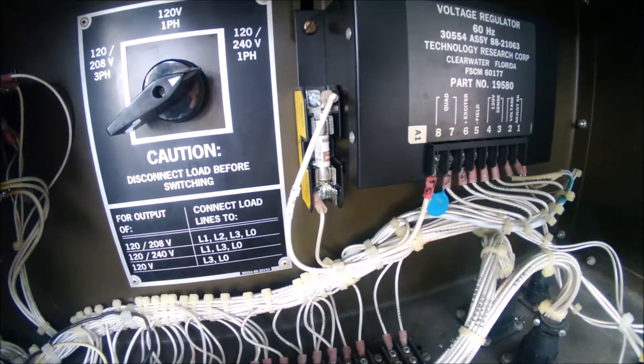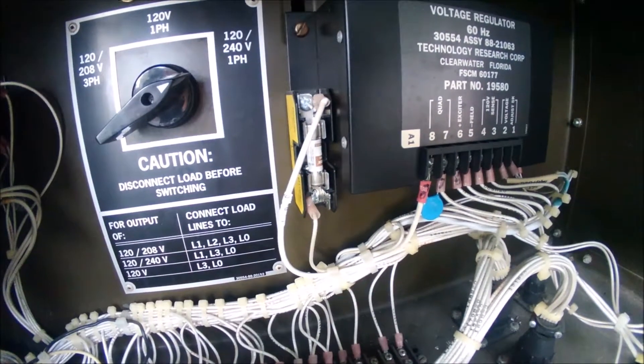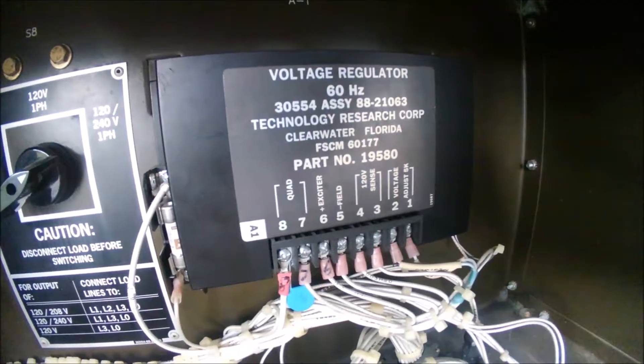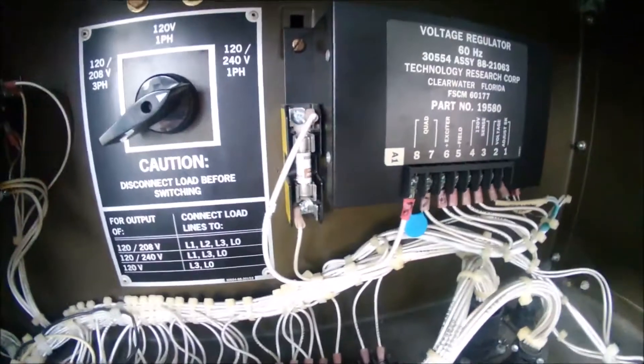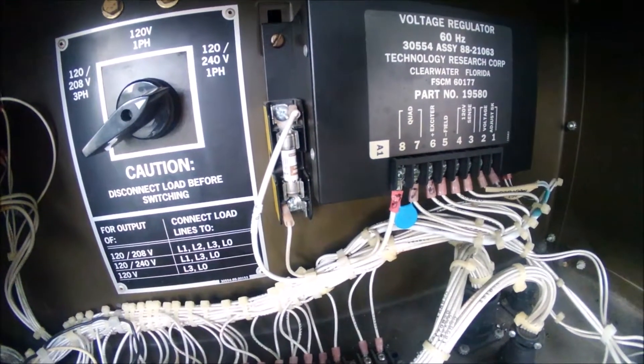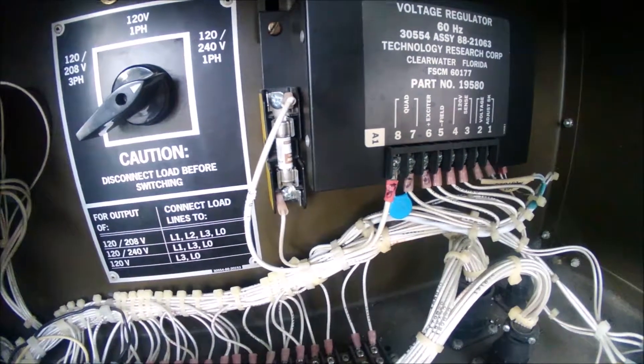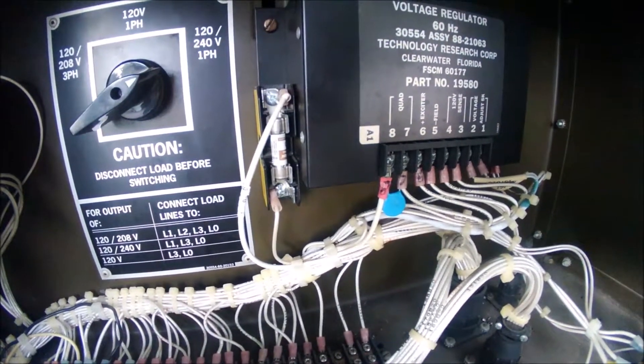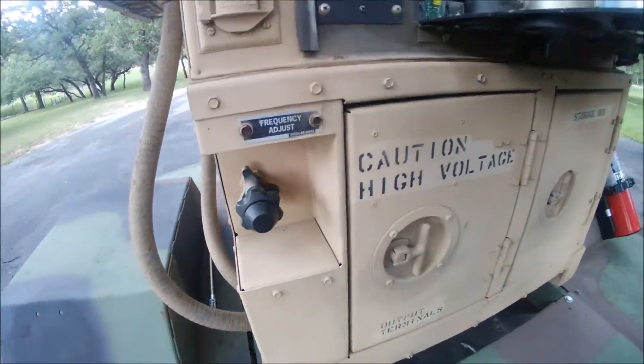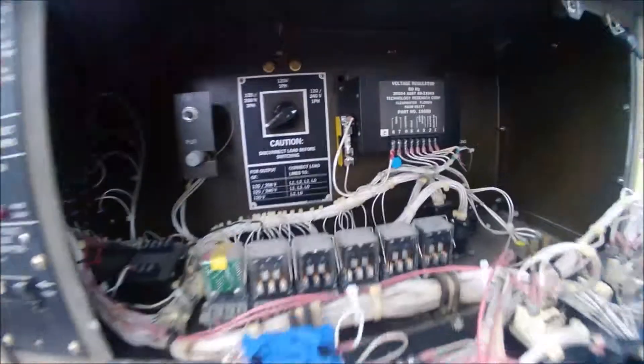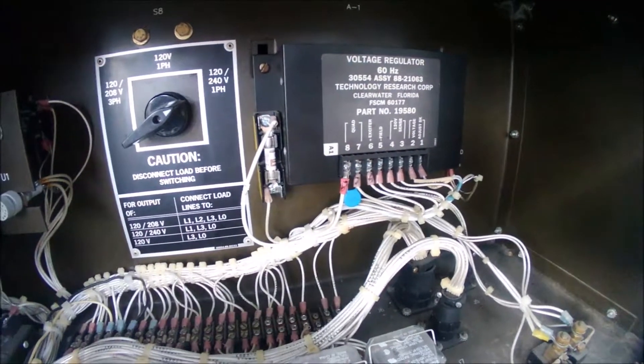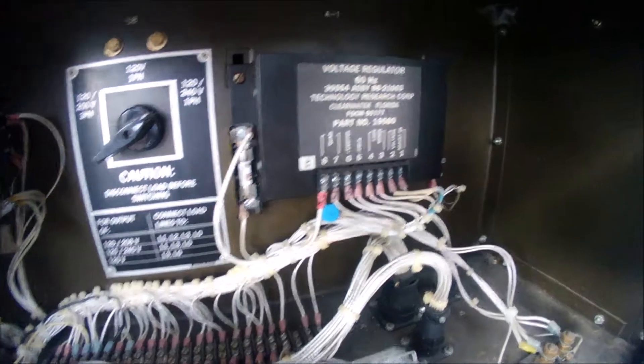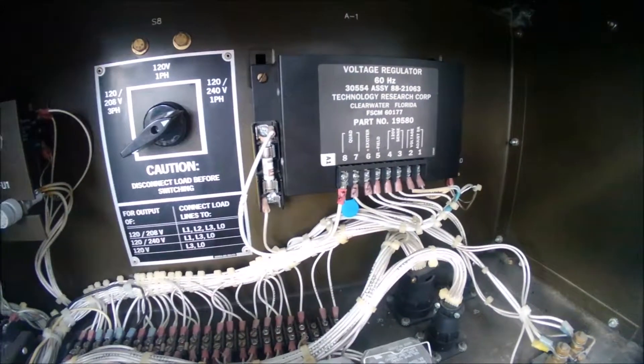In the generator head, stators kept going bad one after another. The actual problem is the voltage regulator goes bad, and this protects that from happening. Also, if you have a mechanical frequency adjust on these and you're running under really high current—say you're running this thing right up at the max, like 30 amps at 240 volts—the voltage regulator will try really hard to compensate.